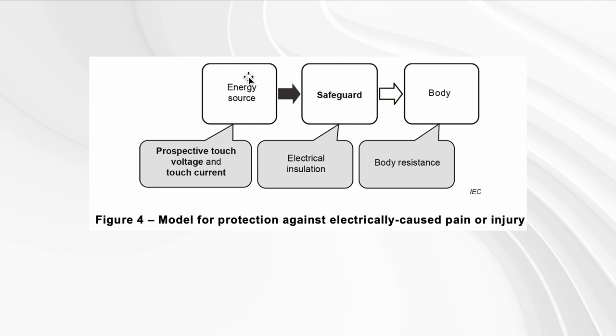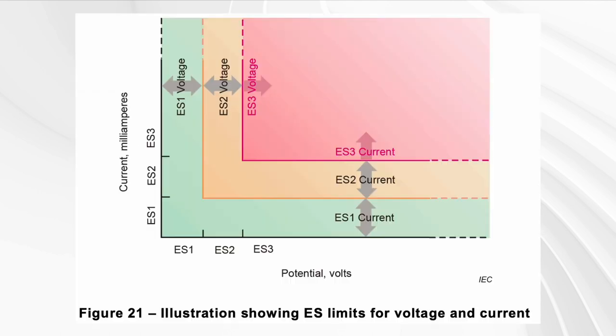The IEC standard provides us with this simple diagram. There's an energy source — and here we're only going to look at electrical sources — and safeguards, typically electrical insulation but not the only type, as we will see. The safeguard prevents the energy source from reaching the body, or at least from reaching it above certain limits.